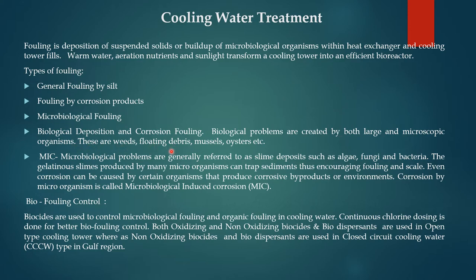Large organisms include weeds, floating debris, mussels, and oysters. Microbiological-induced corrosion (MIC) refers to microbiological problems generally described as slime deposits such as algae, fungi, and bacteria. Due to sunlight, algae, fungi, and bacteria will grow. The gelatinous slime produced by many microorganisms can trap sediments, encouraging fouling and scale, and corrosion can be caused by certain organisms that produce corrosive by-products.